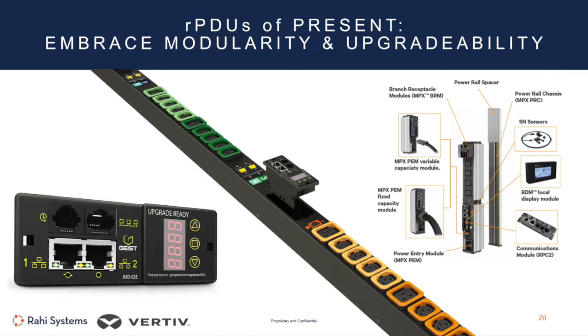Finally, in looking at the rPDUs of present, we'll talk about modularity and upgradability. There are a lot of modular products in the data center, from modular cooling devices to UPSs. The rPDU, understandably, was one of the final products in the ecosystem to embrace modularity. And there are products that use that term modularity with a few different approaches. We talked briefly about hot swappable intelligence cards that can be replaced if they ever fail. Those same cards can be used for field upgrades of PDUs.